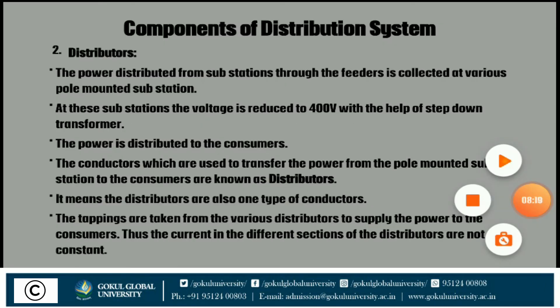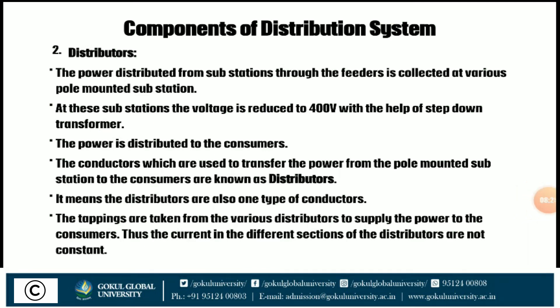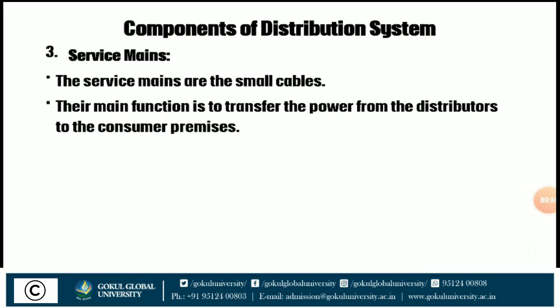Second is the distributor. The power from the substation through the feeder is collected at various pole-mounted substations. At this substation, the voltage is reduced to 400 V. The conductors used to transfer power from the pole-mounted substation to the consumer are known as distributors. Tappings are taken from distributors to supply power to consumers, so the current in different sections of the distributor is not constant. Third is the service mains — these are small cables whose main function is to transfer power from the distributor to the consumer premises.